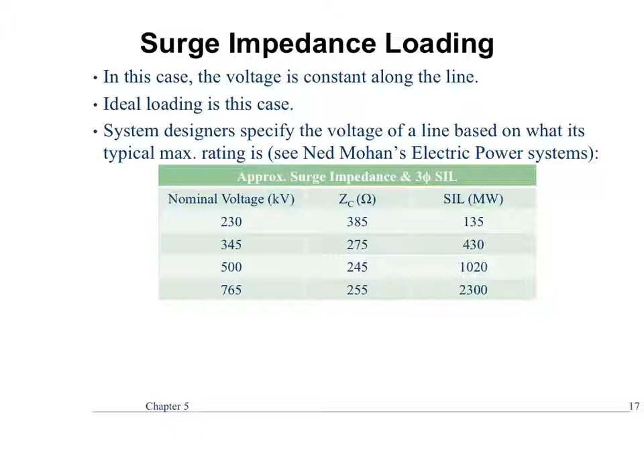Now, this does not talk about contingency analysis, because contingency analysis is too difficult to categorize with just a simple table. You've got people working on PSSE who spend weeks running thousands and thousands of different cases to figure out the worst case contingencies, and sometimes it's not obvious. The more casework you do, the more obvious it gets, but for the rest of us, it's not obvious. But at the very base level, if you have a short line, we talked about thermal, you can get to at least 3 times the SIL rating. If you're a medium length line, so 50 to about 150 miles, you're going to limit that to about 5%. Remember I said 10%, but you always want to be a little tighter, so 5%. You're going to go up to 1.5 to 3 times.